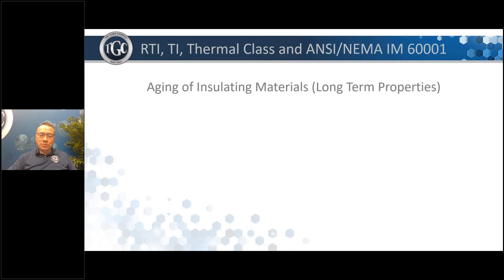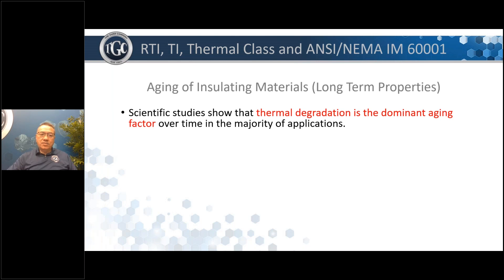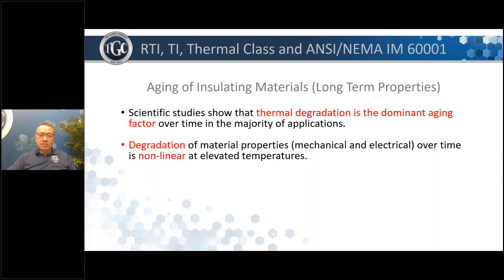So if we want to establish our RTI, that's what UL calls long-term properties. It involves aging of the insulating materials. Scientific studies have proven that thermal degradation is a dominant aging factor over time in the majority of applications. The degradation of material properties can be mechanical, electrical, or both, and over time it is non-linear at elevated temperatures.